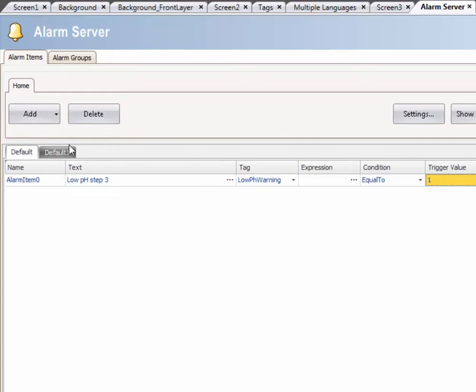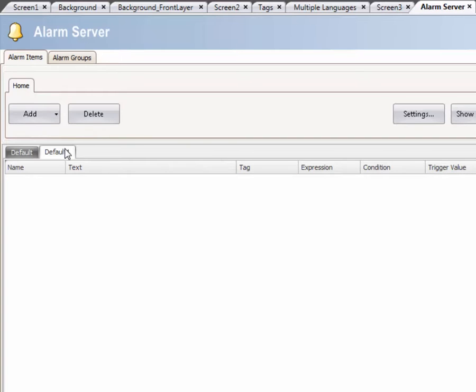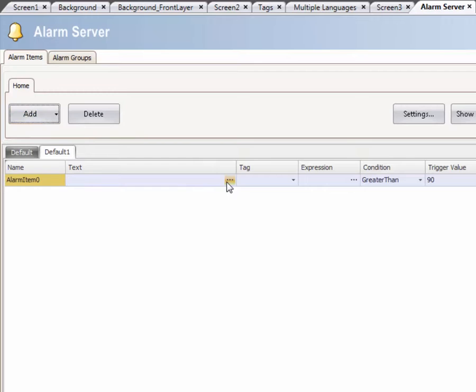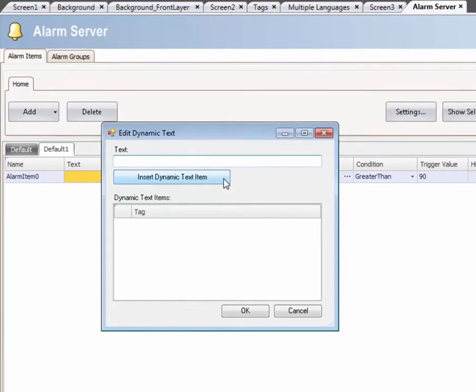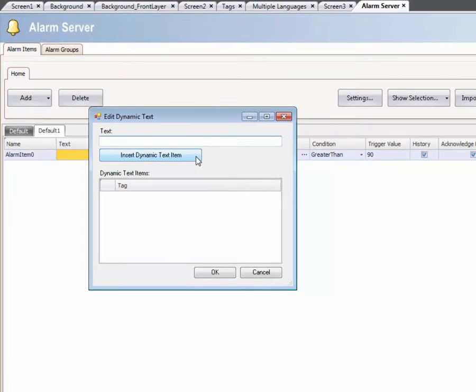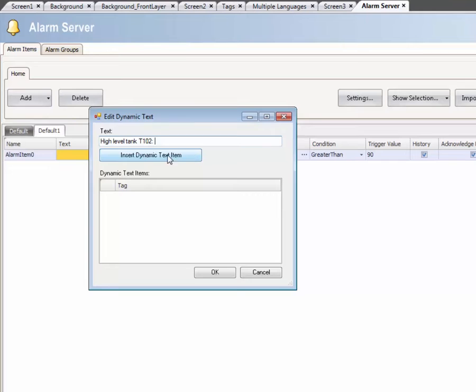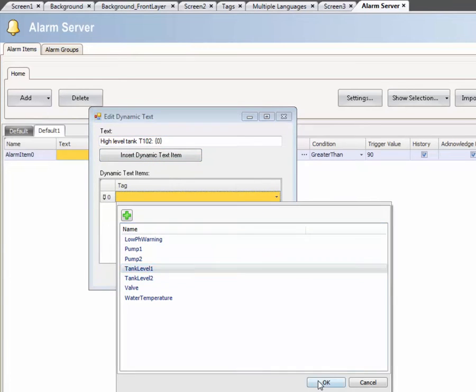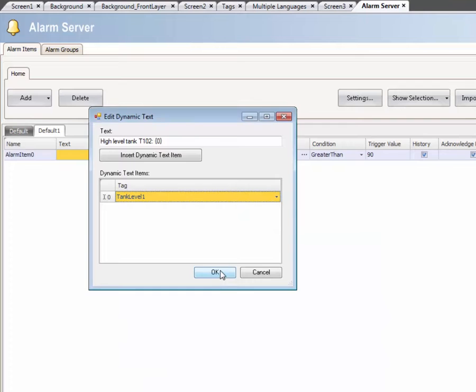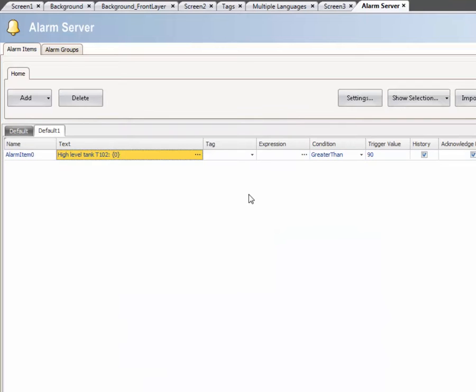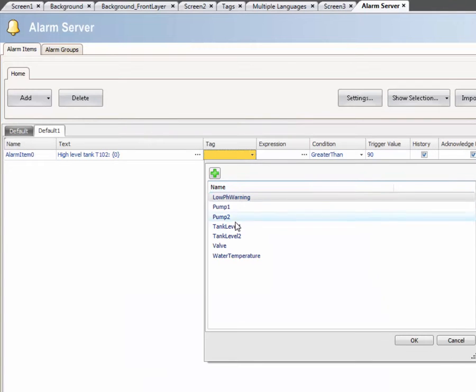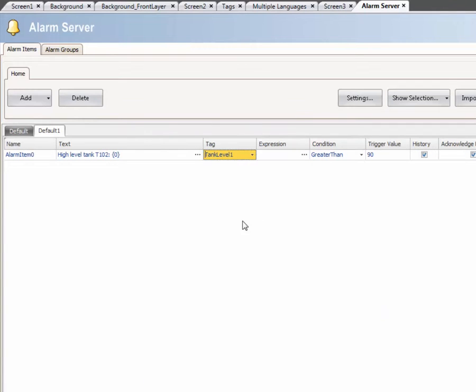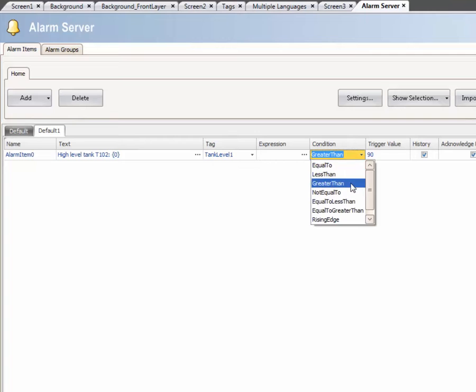Select the second group and add an additional alarm. Click on the Ellipsis button. This enables us to embed dynamic tag values to the alarm text. Click on Insert Dynamic Text Item to add a tag connection. Then select the tag that should be used. Select the tag that should be monitored for that alarm and finally the condition and trigger value.